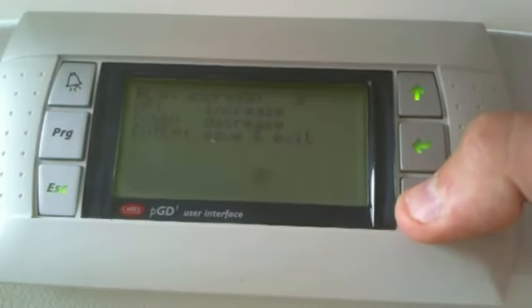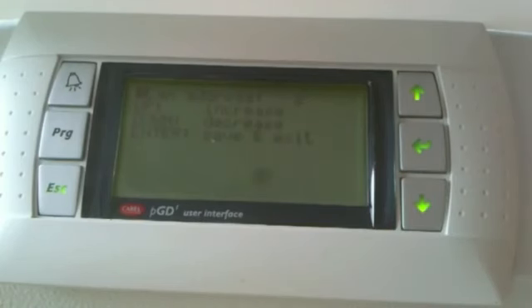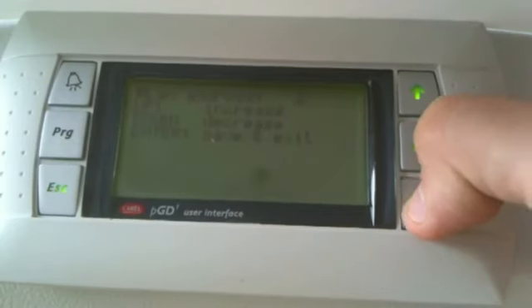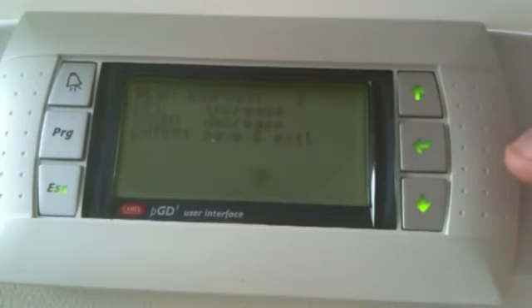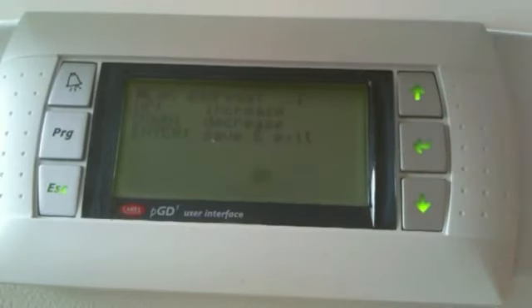Within a pLAN network, each controller must have its own unique address, whereas a display can be configured as shared, thus viewing more than one controller. In this case I only have one controller in the network, so I will assign address number 1. To confirm, I press ENTER.